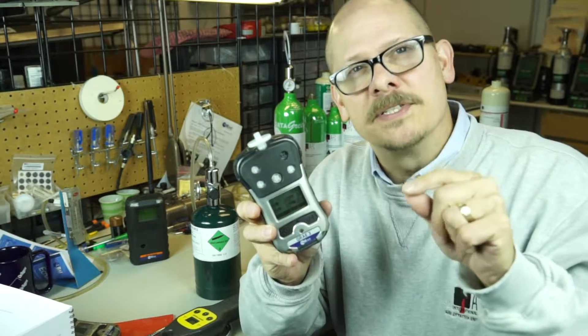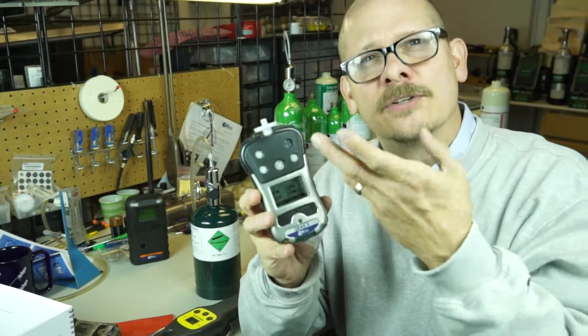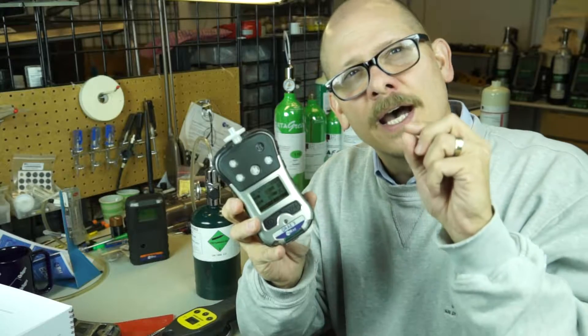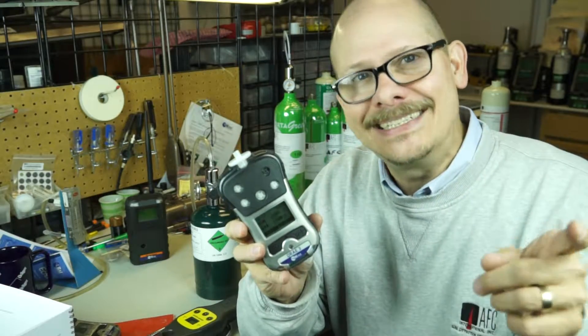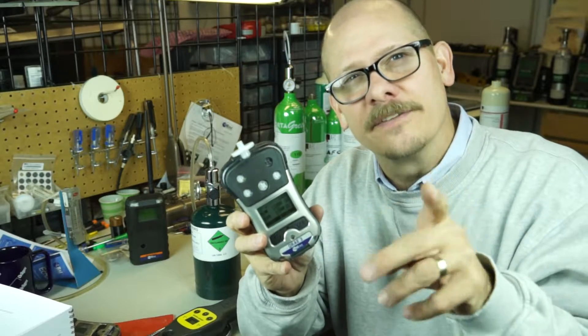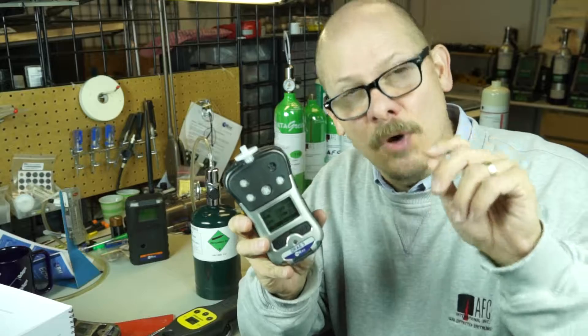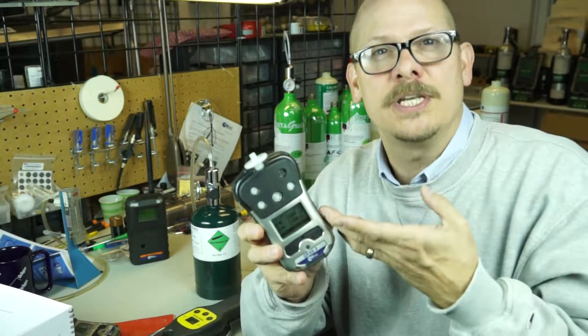For confined space use, it can be any make or manufacturer — MSA, Industrial Scientific, Draeger, RAE Systems — it doesn't really matter. That LEL sensor just can't get down to the low end to be an effective leak detector. The key thing here is the definition of a leak detector: leak detector means very, very small concentrations — small concentrations that you can even smell before the detector will see.